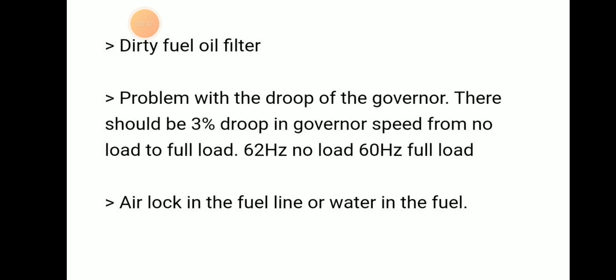Then air lock in the fuel line or water in fuel. These are the reasons for generator voltage fluctuations.